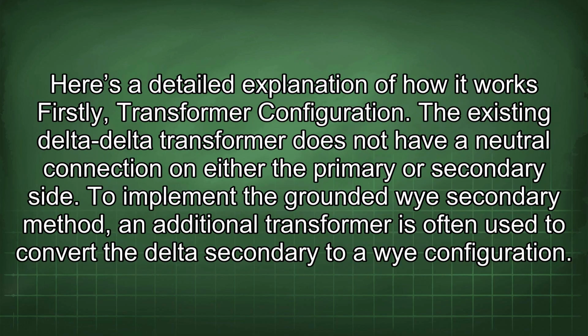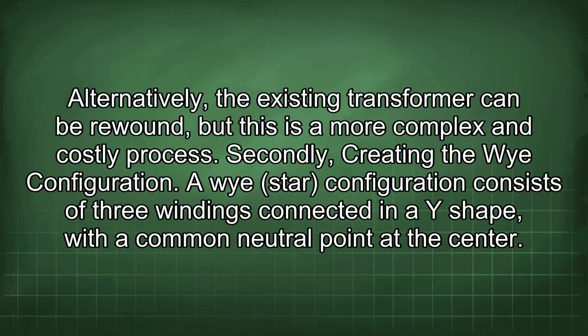Firstly, transformer configuration. The existing delta-delta transformer does not have a neutral connection on either the primary or secondary side. To implement the grounded Y secondary method, an additional transformer is often used to convert the delta secondary to a Y configuration. Alternatively, the existing transformer can be rewound, but this is a more complex and costly process.